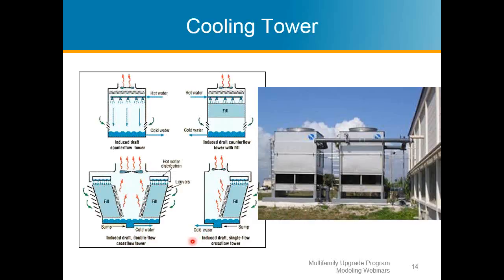Another thing to know is that the water you use to refill that is going to have impurities and particles in it. So there's a bleed valve on the bottom, and they will bleed off some of that water so the system doesn't get all dirty and crummy. That's from the fill water that comes in, or the street water, or whatever you want to call it.